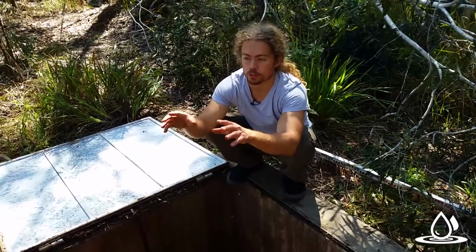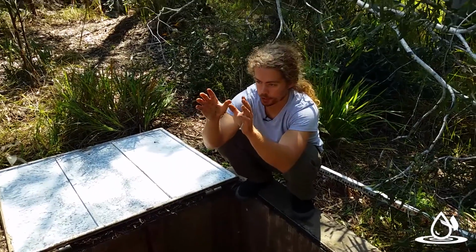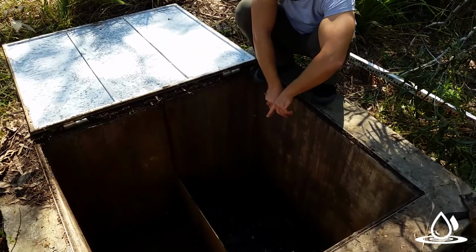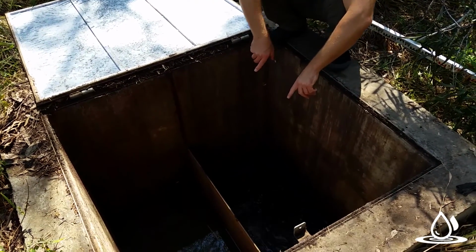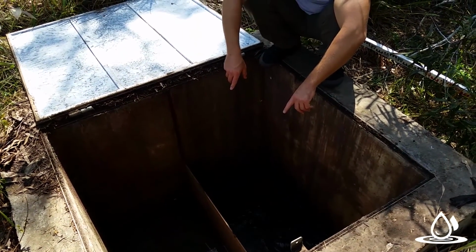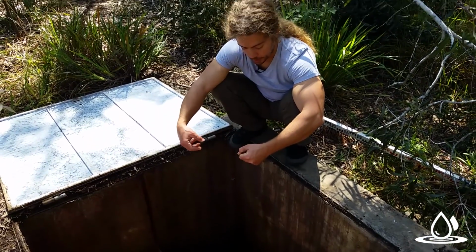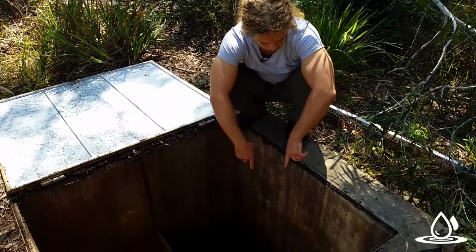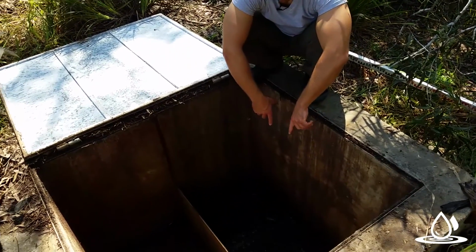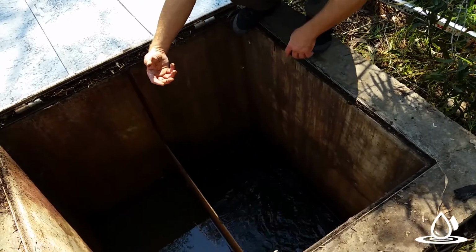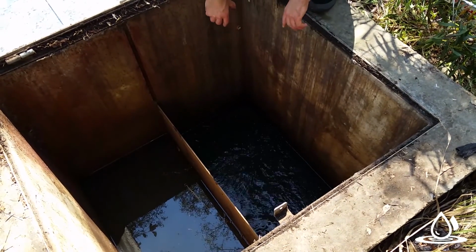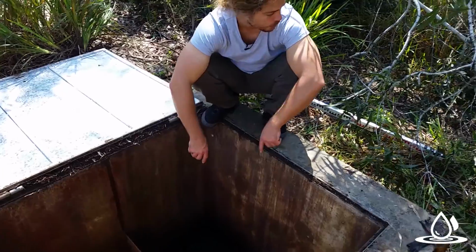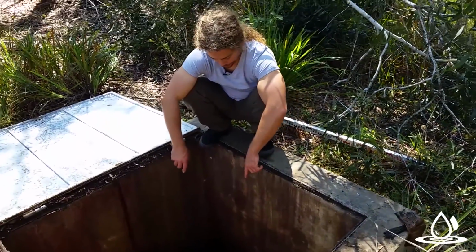So this is the process of investigating this. I'm looking at the wetland itself. I'm looking at the water coming in. I'm looking for the various holes in the riser arrangement. Are they freely draining? If they are, okay, can they drain back down? Okay, what's happening on this downstream side of the pit? Is that water level low enough that those holes can drain through, or have we got a backwater effect happening? And we've got a bit of a backwater effect happening with this wetland.